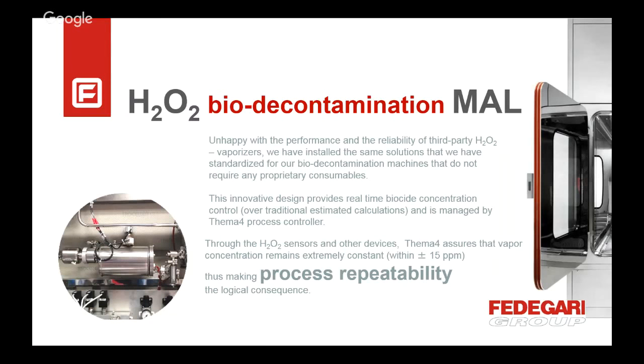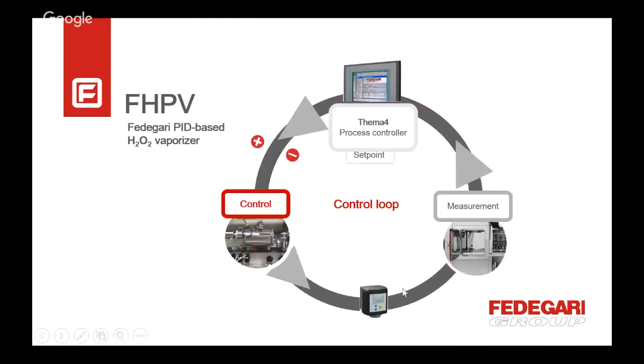The key point of this technology is that we are working on a feedback basis. We have a detector of high concentration hydrogen peroxide. This detector measures the concentration of hydrogen peroxide inside the chamber and sends a signal to the controller, the Thema4 process controller. The controller checks the set point and, according to the set point, adjusts the strokes of the dosing pump that is on board of the vaporizer. So we are able to have an excellent control of the concentration inside the chamber, with plus or minus 20 ppm.